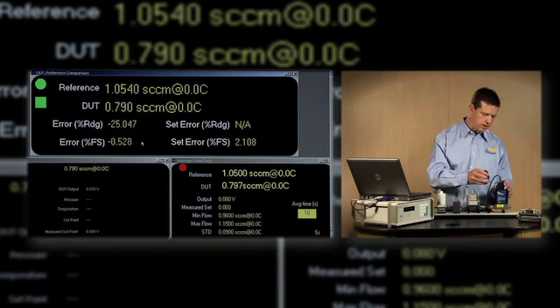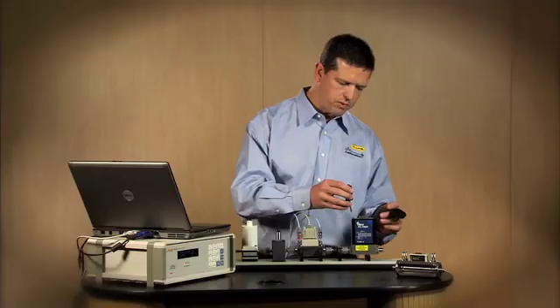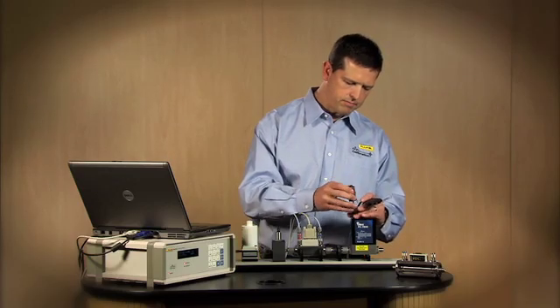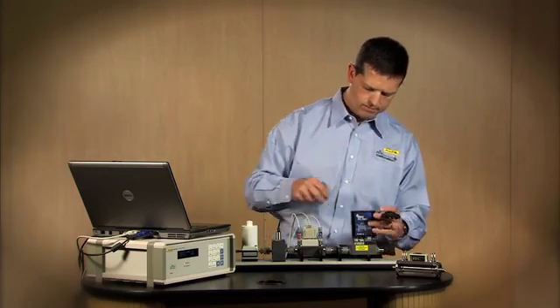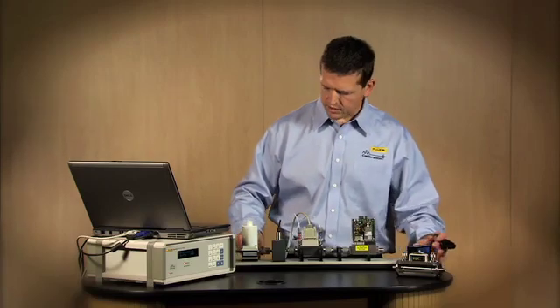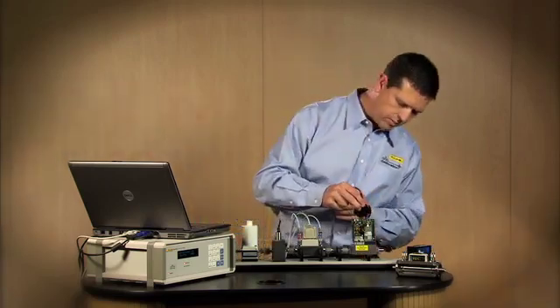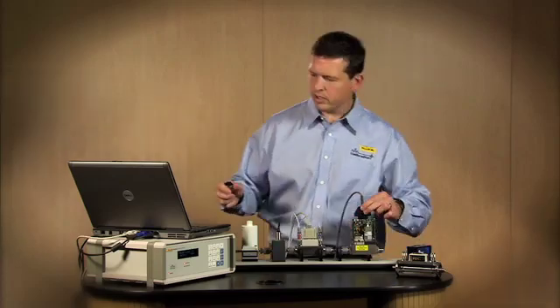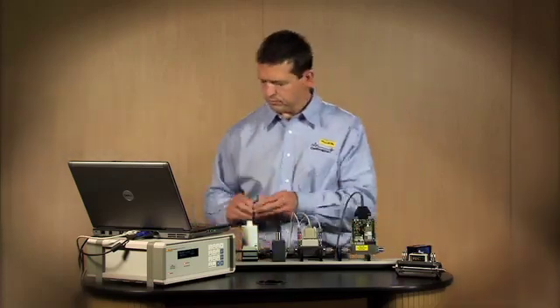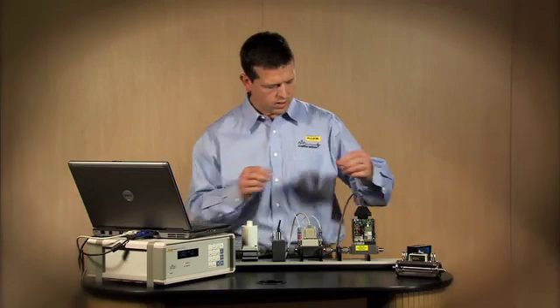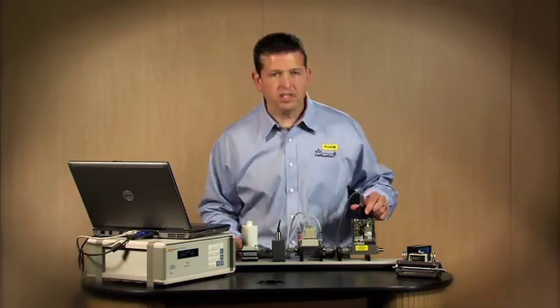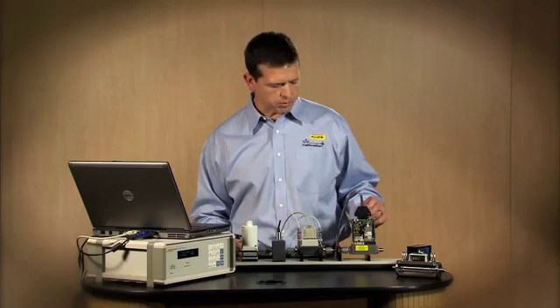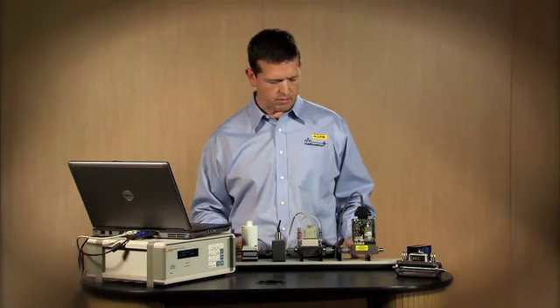Now to make the adjustments, I'm going to finish removing the cover from the MFC so I can access the potentiometers to make adjustments. I'll replace the MFC cable so it can communicate with the Molbox1+. I've identified three potentiometers that adjust the MFC's reading at 0%, 50%, and 100% points.